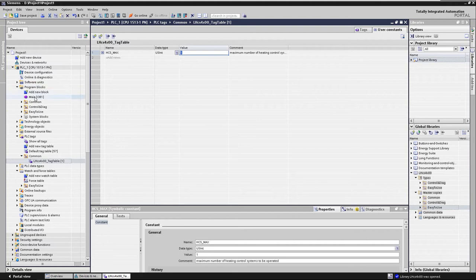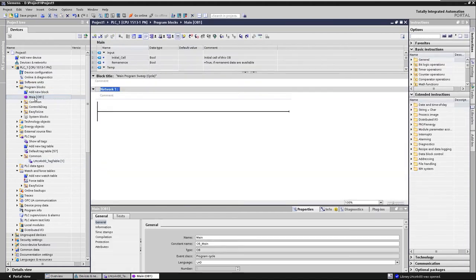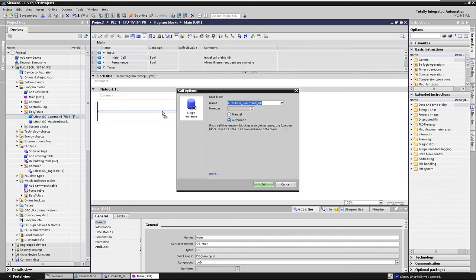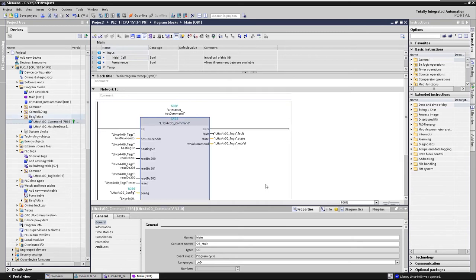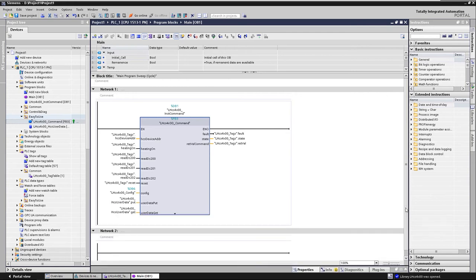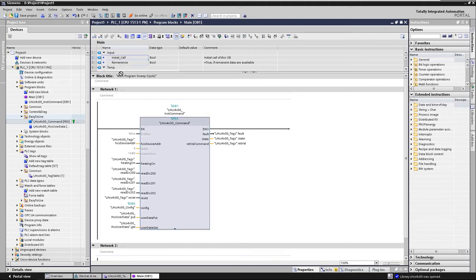The command function block from the easy-to-use folder is called in OB1 main. Drag it into OB1 and generate an instance data block for the FB. The interface parameters are automatically interconnected. Only the hidden parameter, first run, must be supplied with the interface parameter initial call of OB1.